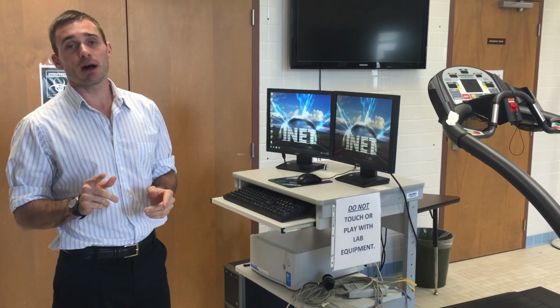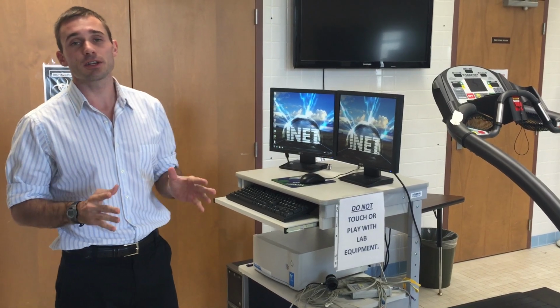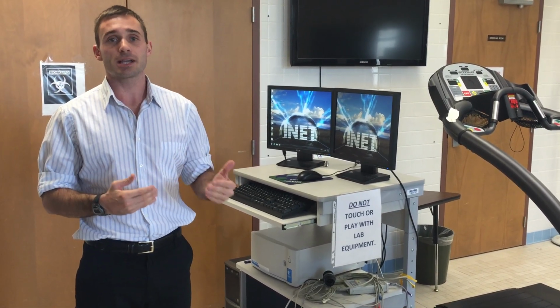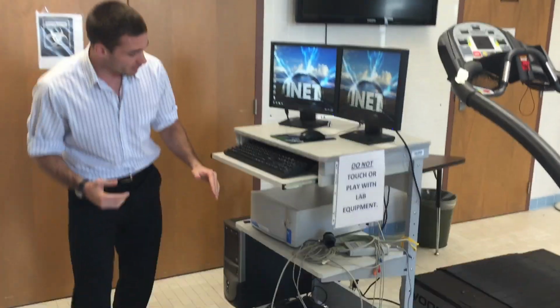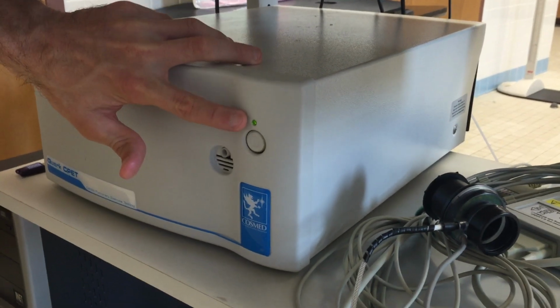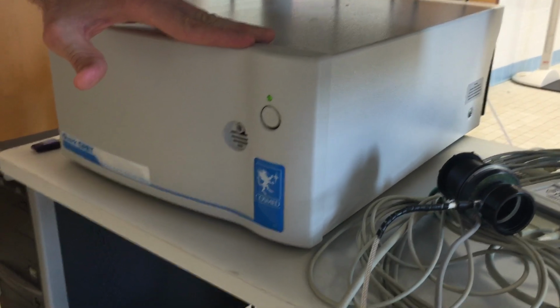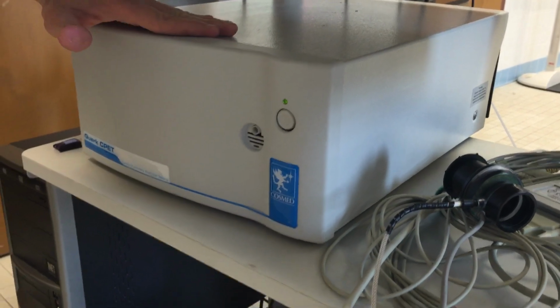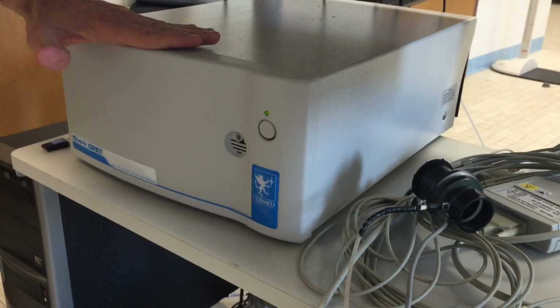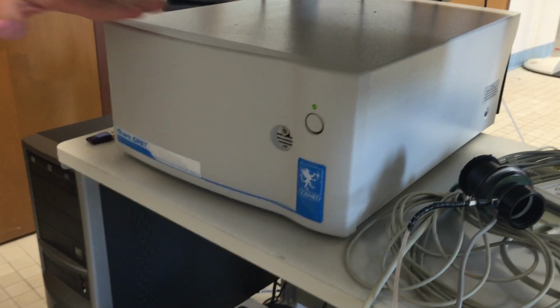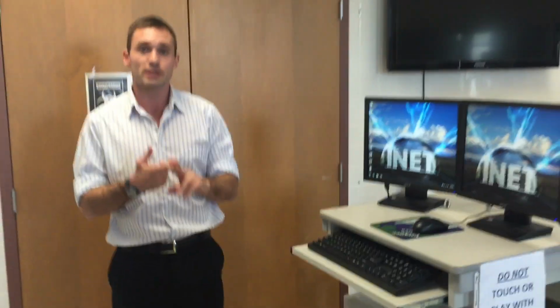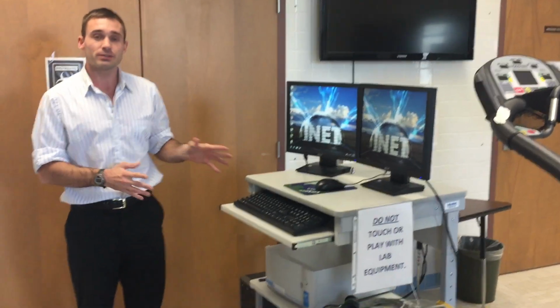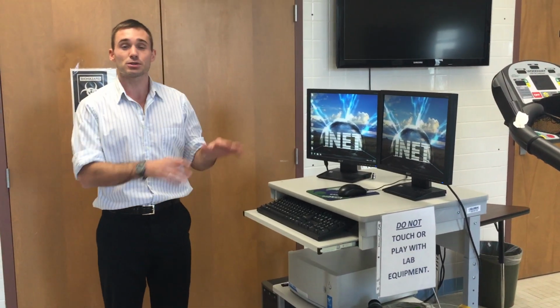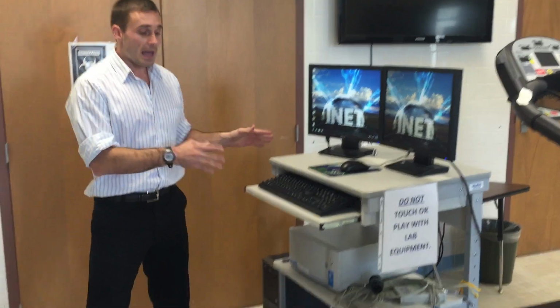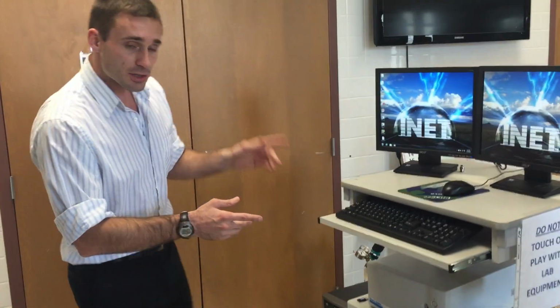The first thing we need to keep in mind is that the equipment takes about 30 minutes to warm up before we can actually start the calibration process. So if we focus in on here, this is our CosMed unit. You see our start button here in the front. You see the green light is on. We came and turned it on early. It's been about 30 minutes now since we turned on the unit, so we avoid the waiting process, but make sure that if you're going to come in and test, either working with a class or with research subjects, that you provide yourself enough time to not only turn on the unit, but make sure that you have time to calibrate as well.